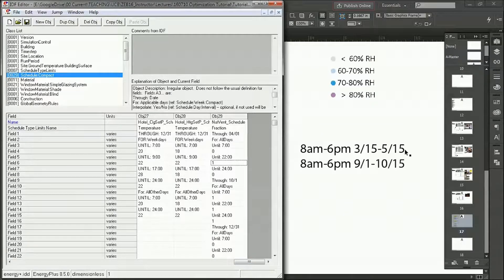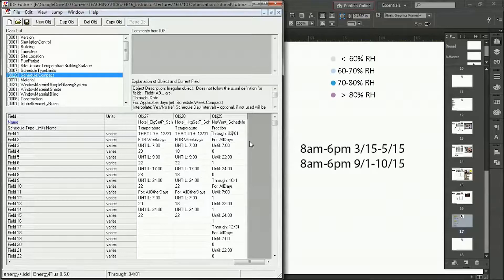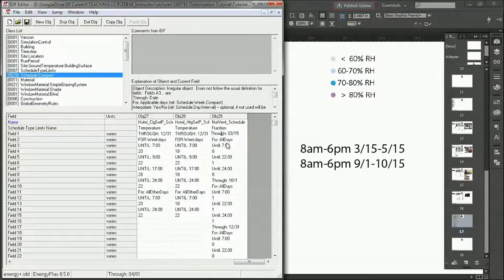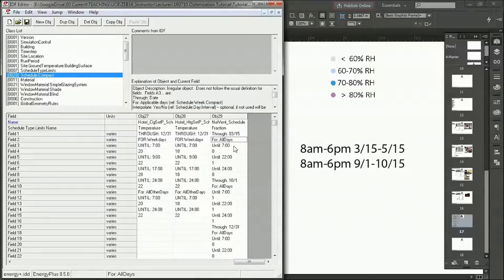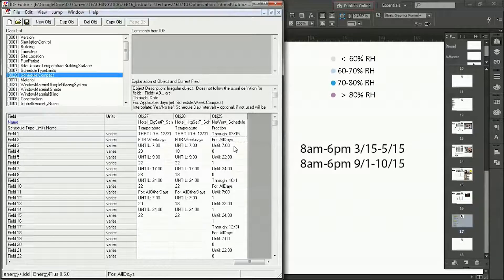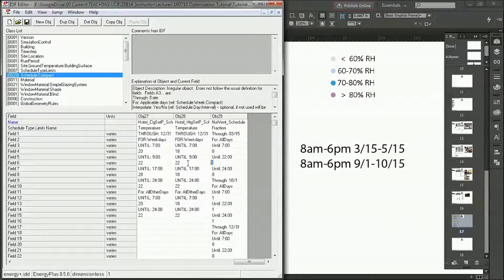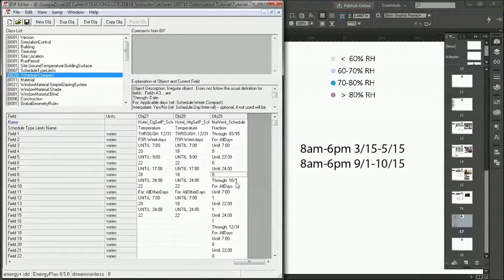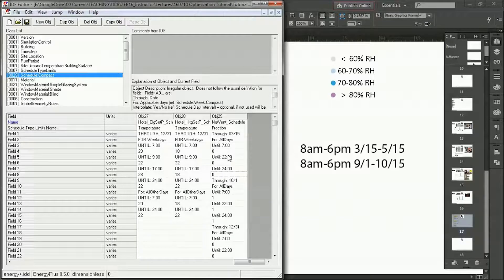So to program this, we'd say through March 15th for all days, we don't want any ventilation. So I can just go through, and the easiest way is to program all three of these to 0, so we're good. So we'll just get heat during those times.